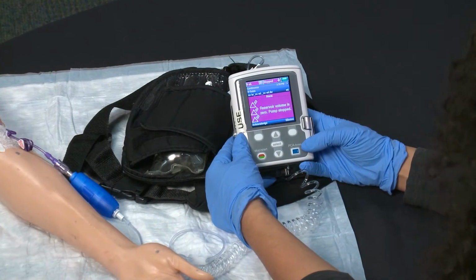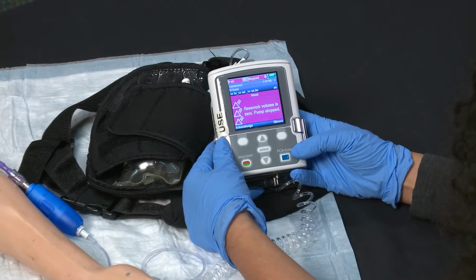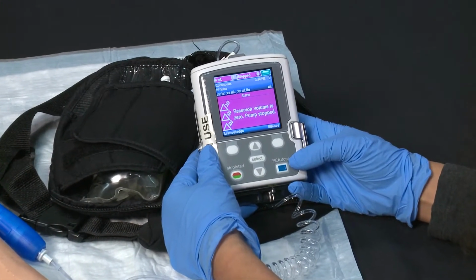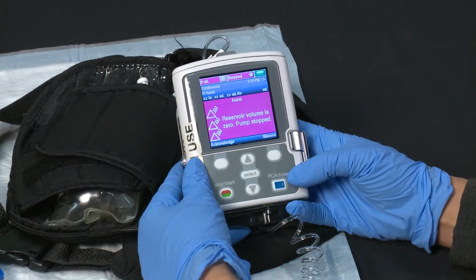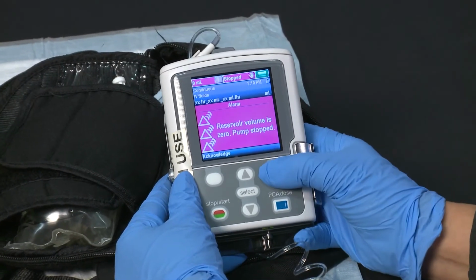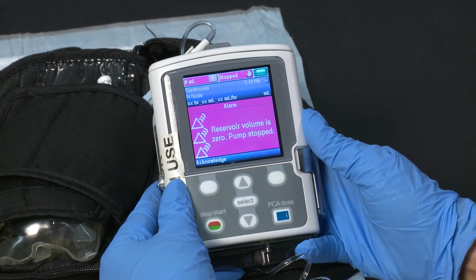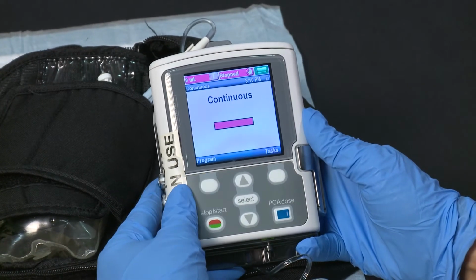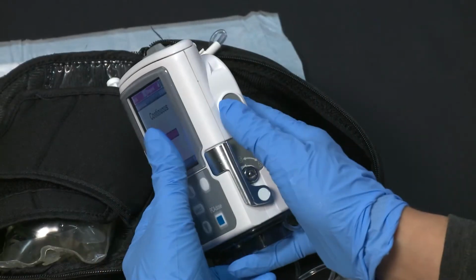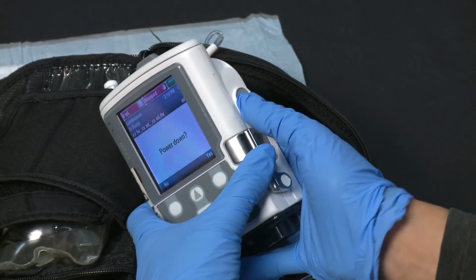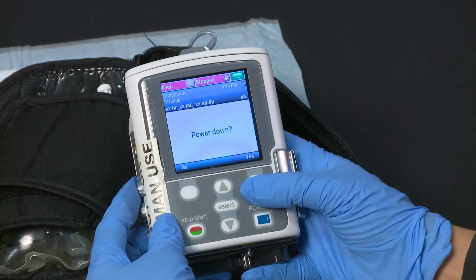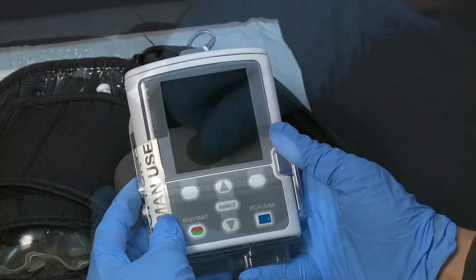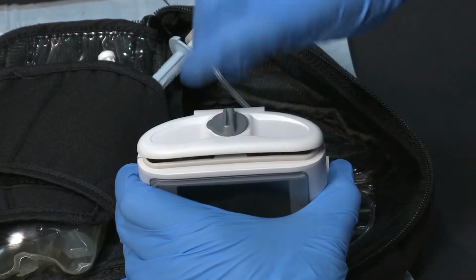When the infusion bag is empty, you will hear beeps, and the pump screen will show reservoir volume 0, pump stopped. Press Stop to silence the alarm. Press Acknowledge. On the right side of the pump, press the power button, then press Yes to power down pump. Remove batteries from the pump.